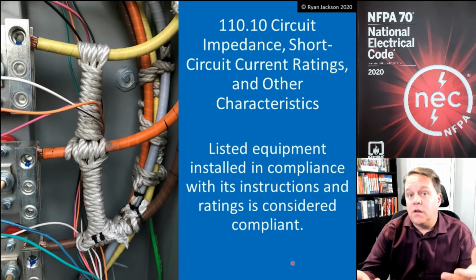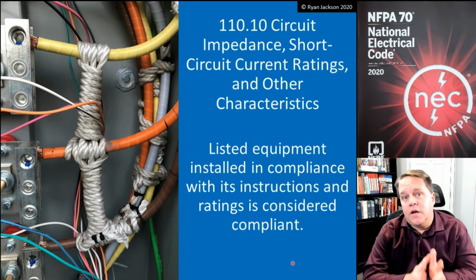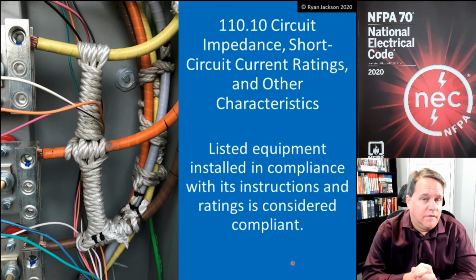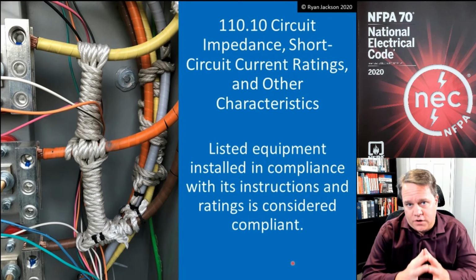So something kind of like this. So do I have to brace my conductors and lash my conductors like this? Yes, if the instructions of the equipment tell me. Why would the instructions of the equipment tell me? Well, because that's part of how the equipment gets its short circuit current rating.